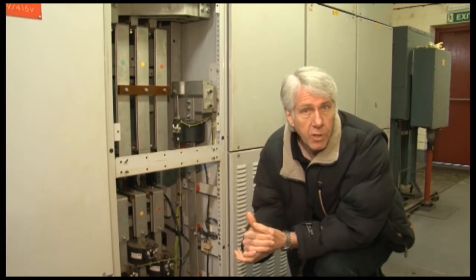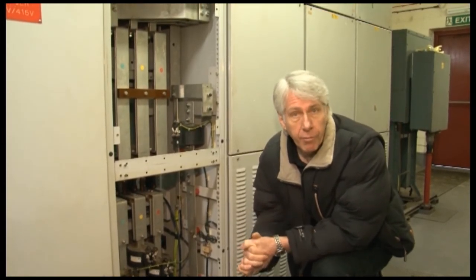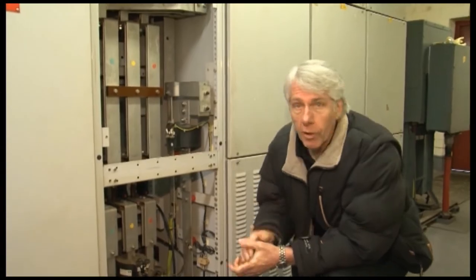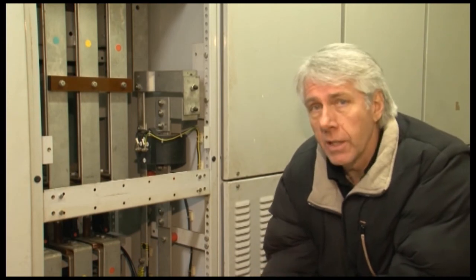Some devices, such as bolted links, are allowed in the reference conductor. The neutral earth link in this distribution board being typical. However, devices such as fuses and semiconductors cannot be relied upon to maintain integrity and must not be installed.